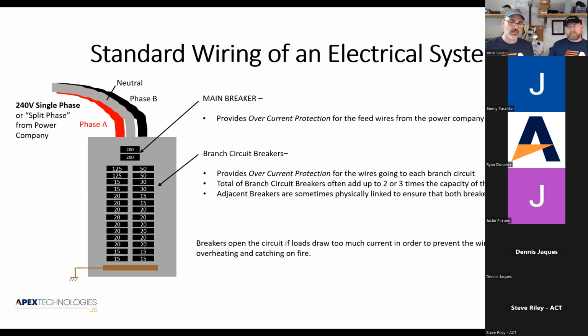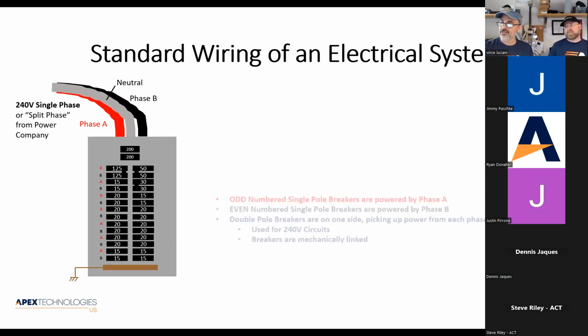This is kind of a gut call from the electrician. They have a lot of experience and they kind of know what to put on what phase, and they're going to do some phase balancing. You really want to pull from the 2 phases as evenly as you can. It doesn't have to be exactly perfect, but you want to do that. So that's kind of how it works. When you look at your breaker panel, if it adds up to more than the main breaker, that's not the end of the world.